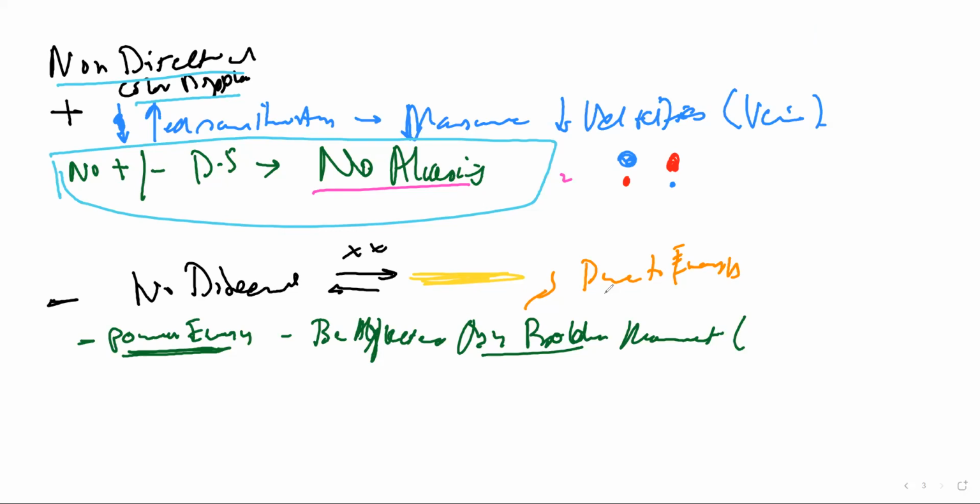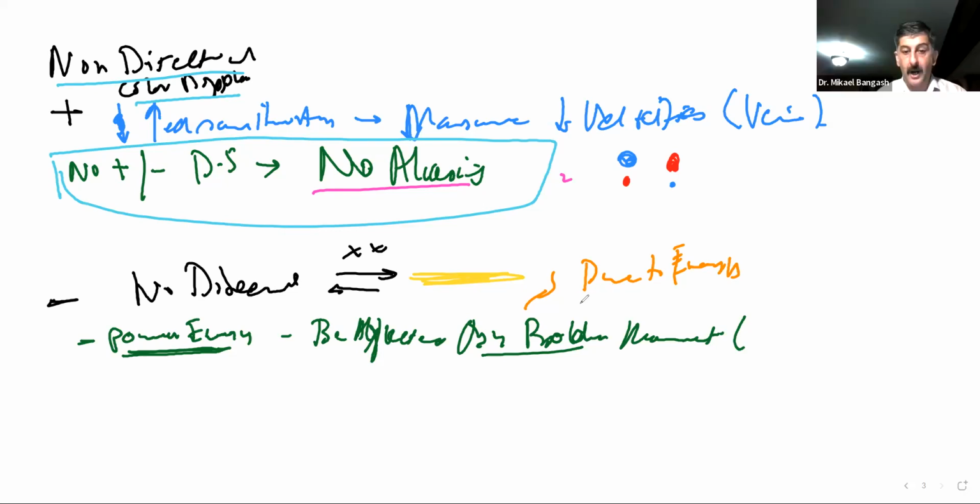Yes, it did. So that body motion, or the energy that was used to cause the motion in the limb, for instance when we're scanning the blood vessels or trying to check blood flow in the arm, may interfere with your power Doppler. The blood flow was a result of energy, and the body movement was also a form of energy.